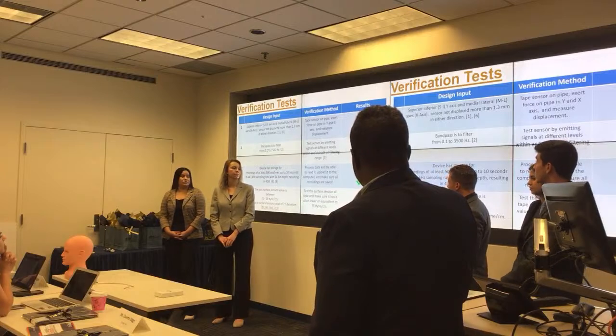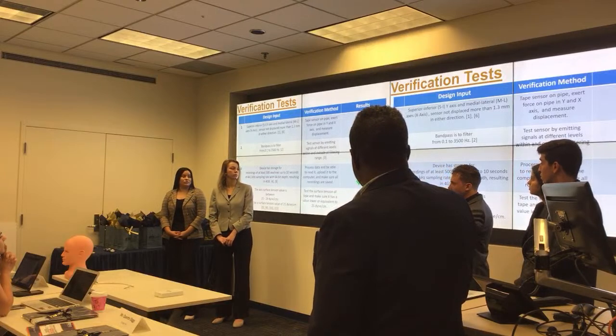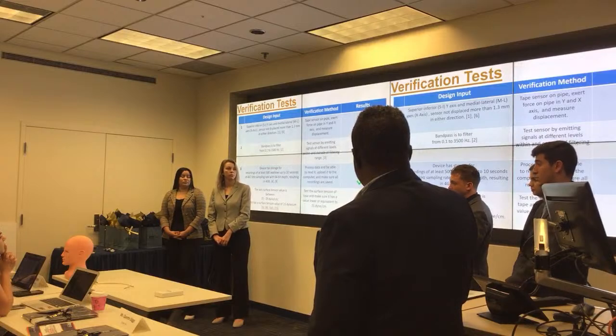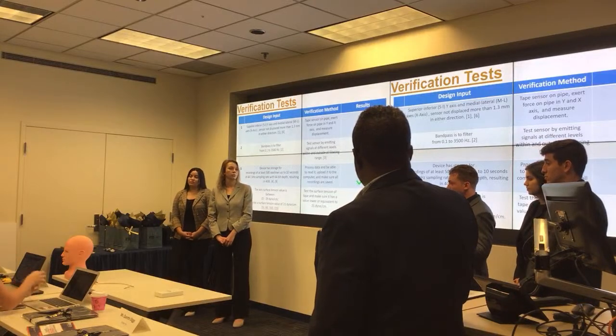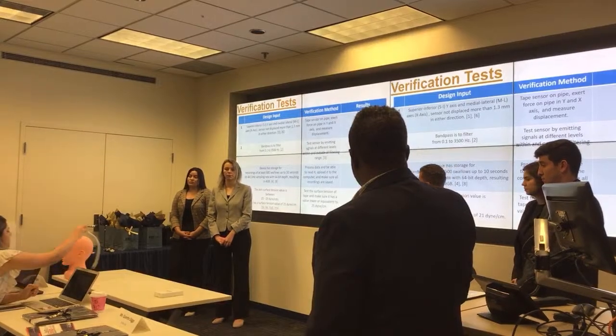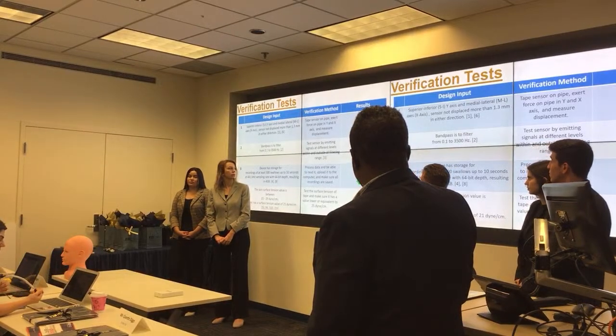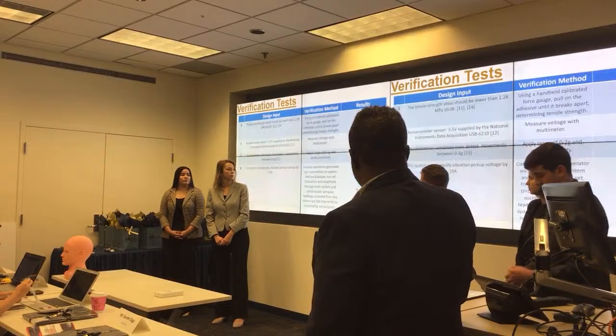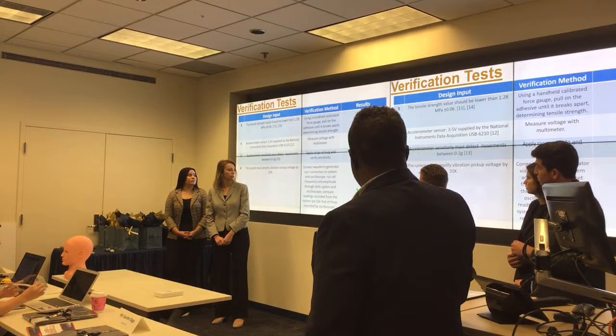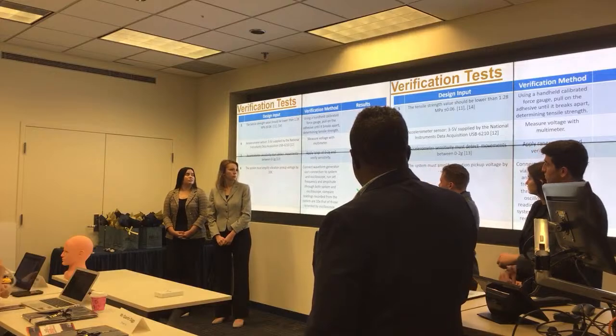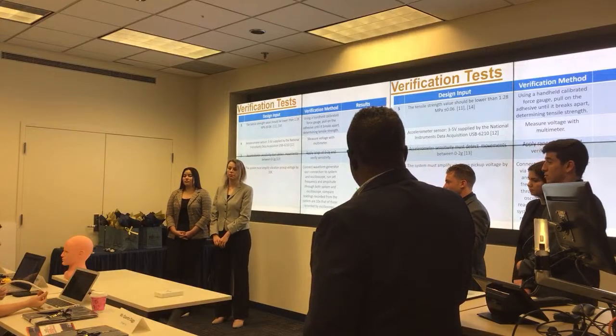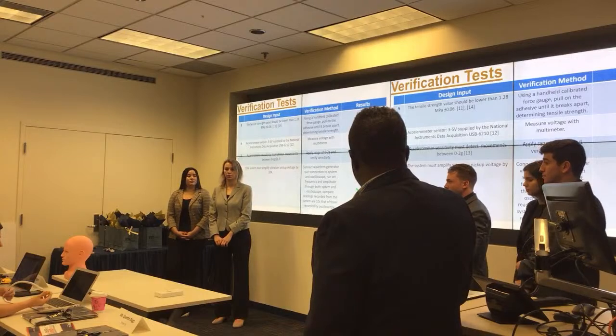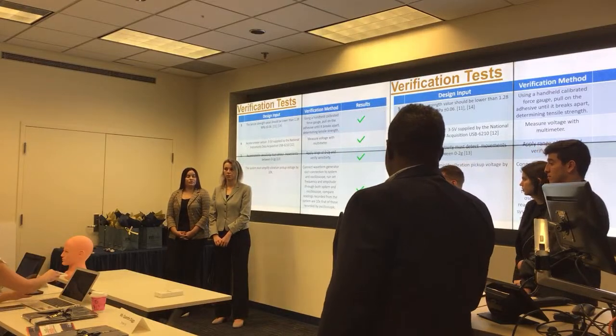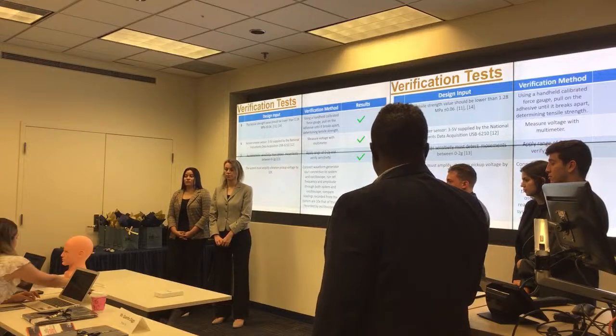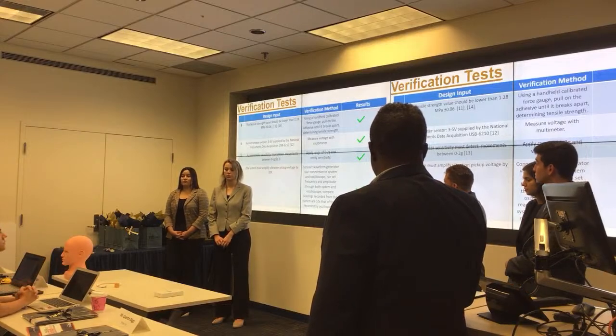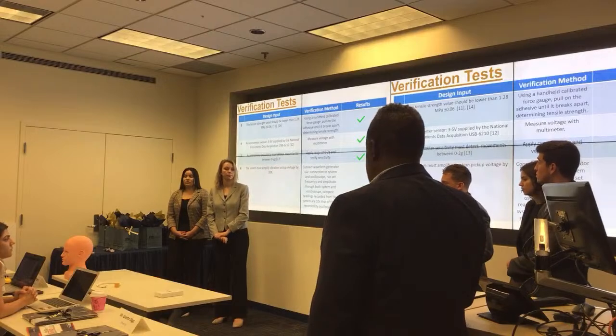We also did protocols in relation to the actual signal that we were receiving, to make sure that we were receiving the actual signal that we wanted and it was being processed. So it was the bandpass filtering. We also did additional verifications, for example, the sensitivity of the accelerometer. So we tested forces from 0 to 2 Gs on the accelerometer, proving that the forces that we were emitting on our system were actually the ones that we were receiving. And we actually passed this protocol as well.